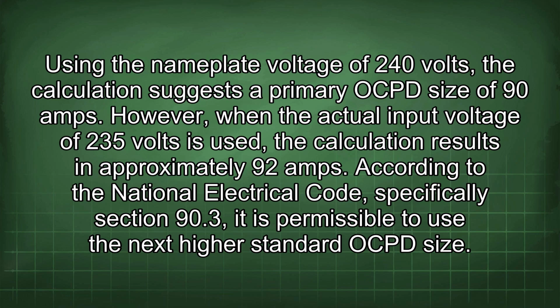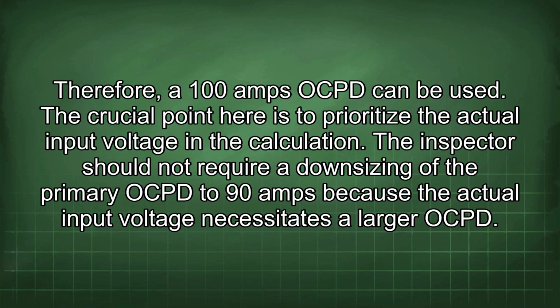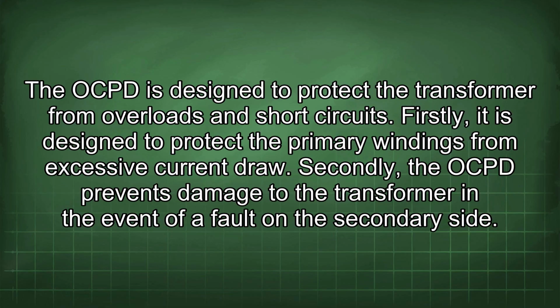According to the National Electrical Code, specifically Section 90.3, it is permissible to use the next highest standard OCPD size. Therefore, a 100 amps OCPD can be used. The crucial point here is to prioritize the actual input voltage in the calculation. The inspector should not require a downsizing of the primary OCPD to 90 amps because the actual input voltage necessitates a larger OCPD. The OCPD is designed to protect the transformer from overloads and short circuits.